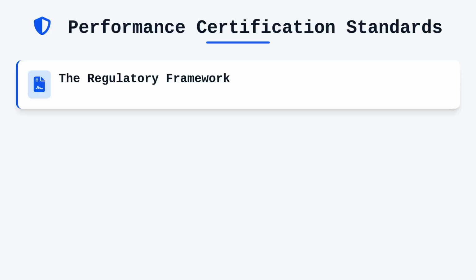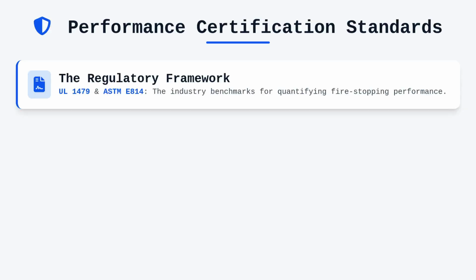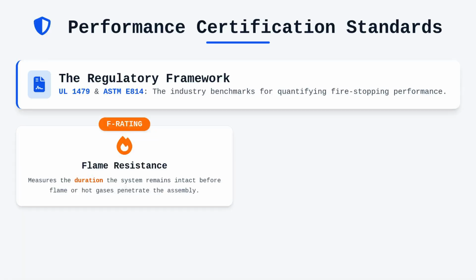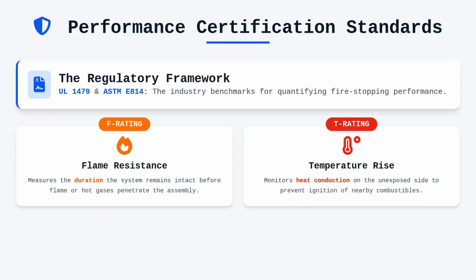Testing and certification standards like UL 1479 and ASTM E814 provide the framework for how we quantify the performance of these systems. The F rating, or fire rating, tells us the duration the system remains in place before flame or hot gases pass through the assembly. However, the T rating adds a critical layer of data by measuring the temperature rise on the unexposed side, ensuring that the sealant does not conduct enough heat to ignite nearby combustibles.